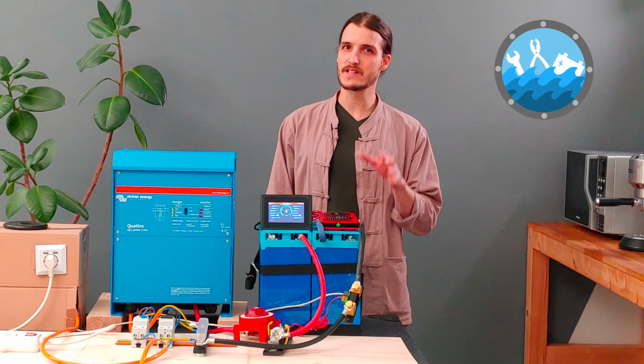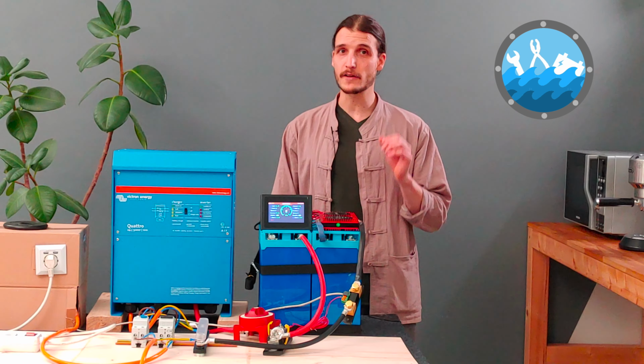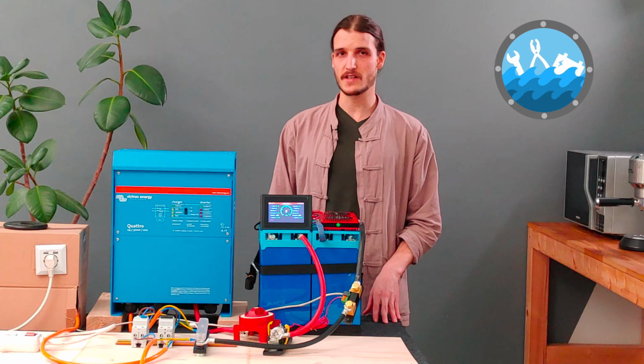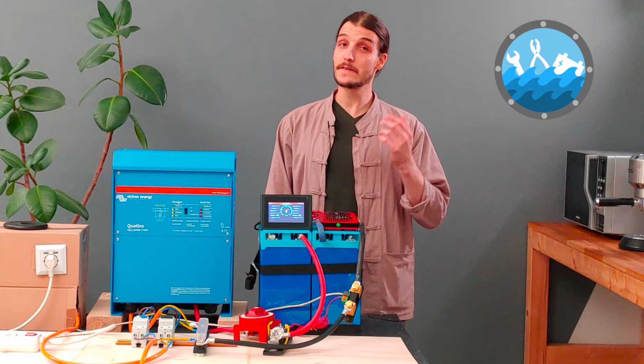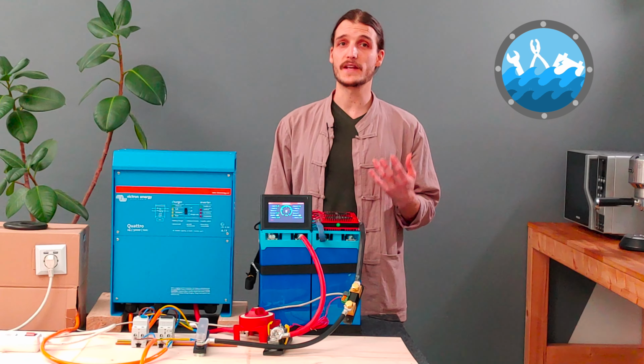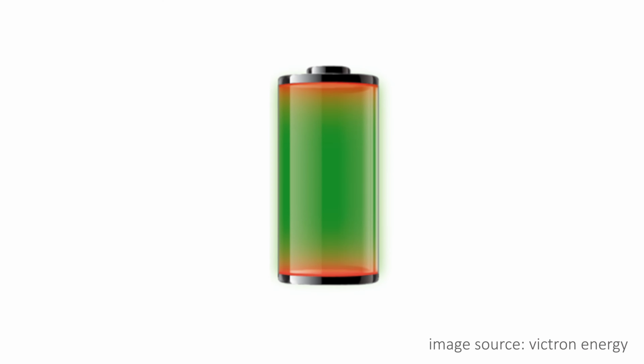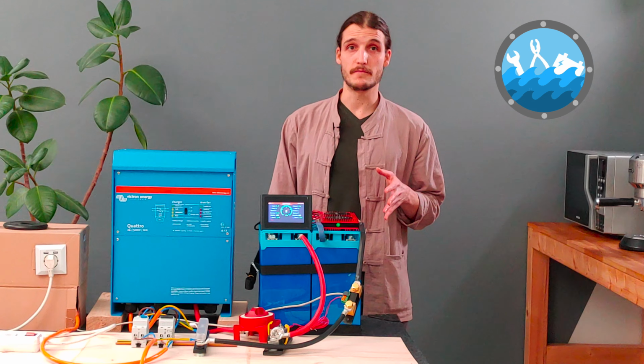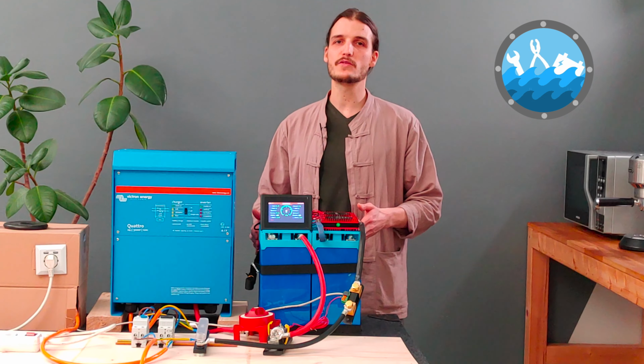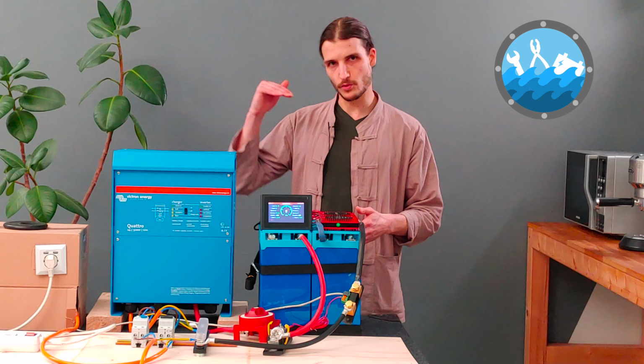When I said 5,000 cycles and more out of a properly configured battery, I put the emphasis on properly configured. Lithium batteries tend to live longer if you operate them within a certain range of state of charge, or SOC, meaning that you don't fully charge or discharge them at each cycle. Instead, you only use them at, let's say, 90% to 30%.